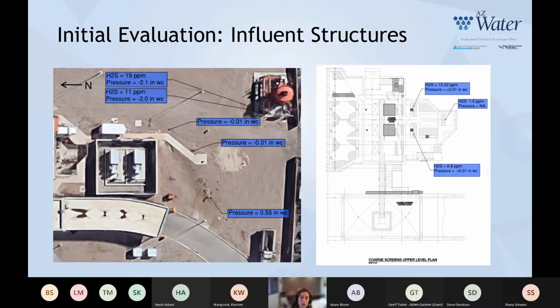Foul air from the influent structure is drawn and treated through the biotrickling filter. The wastewater in the structure is not exposed to ambient air, and there were no noticeable odors in this area. Fan draft from these structures was adequate to limit fugitive emissions, as shown by the pressure and airflow data that we collected from the atmospheric vents at the junction structure. So those are these little guys.